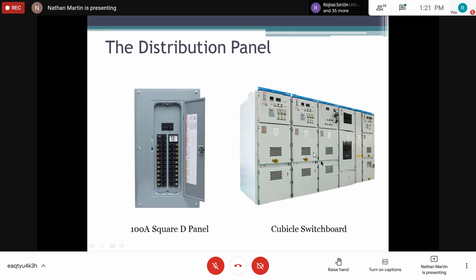which you can't see. Now, this is our standing cubicle switch gear, and inside these switch gears are bus bars. So you'll have bus bars where the cables will either come into the top of the switch gear and go to the different circuits, right? So for this switch gear, your main disconnect is shown right here, where you have the handle to disconnect all of the different cubicles, right? So once you switch this to the off position, all these cubicles will go down, right?